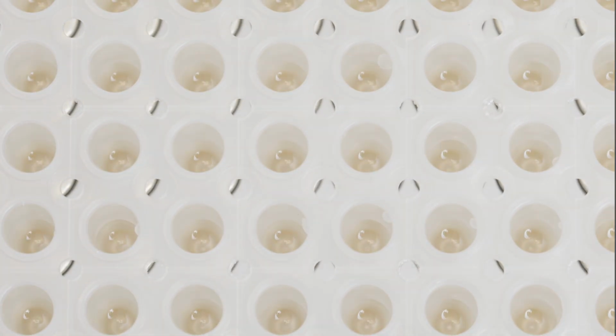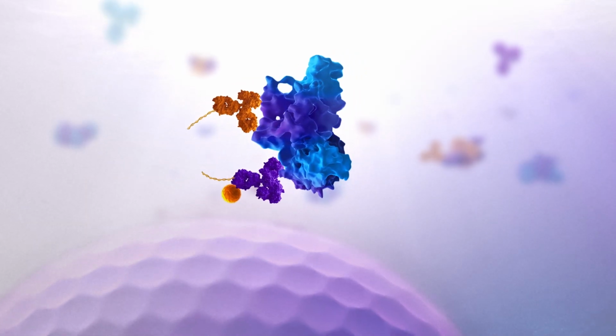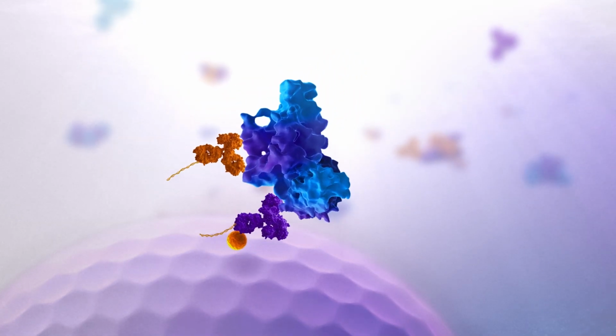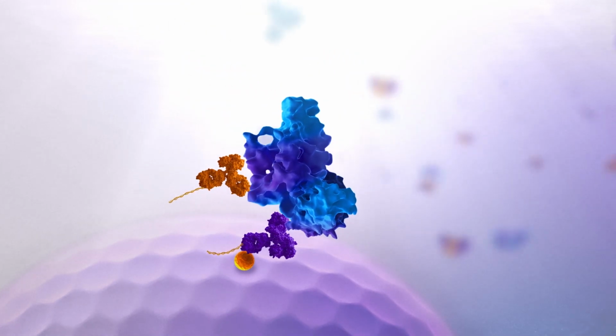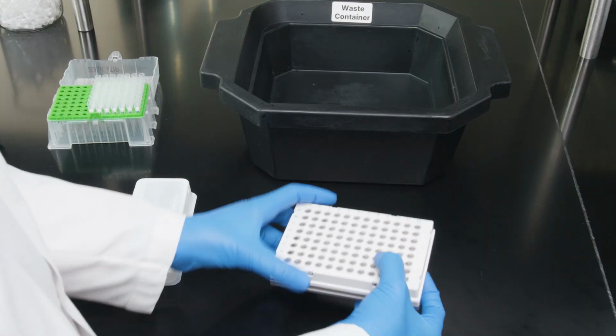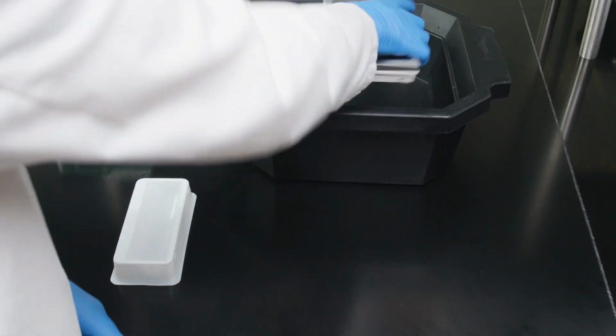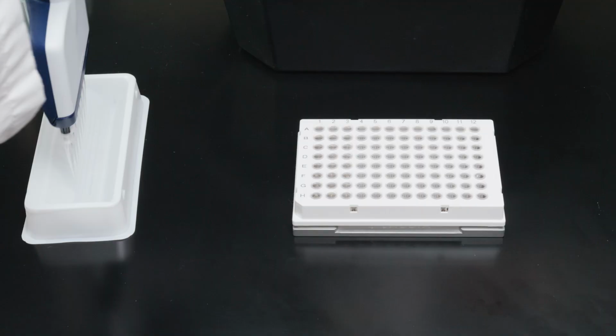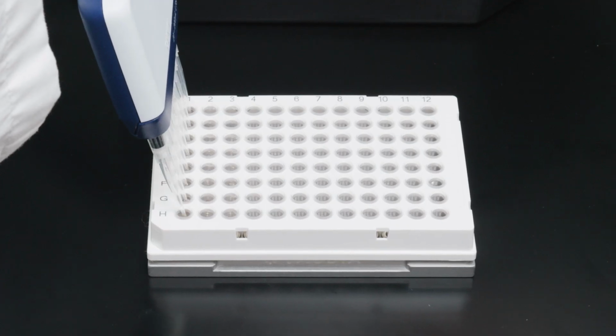Once our incubation is finished, we'll place our plate onto the magnetic rack and make sure it's well seated. The rack will pull and hold the beads with the attached immunocomplexes so that we can wash away any other materials. I'll start the wash by holding the plate and magnetic rack together and flipping it 2 or 3 times into the waste container. Next, I'll add wash buffer to each well.